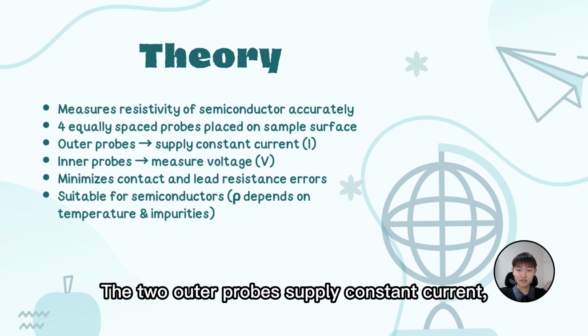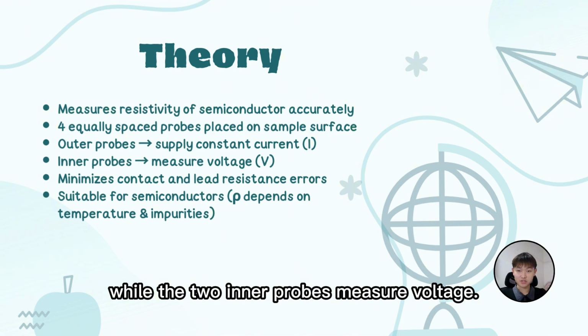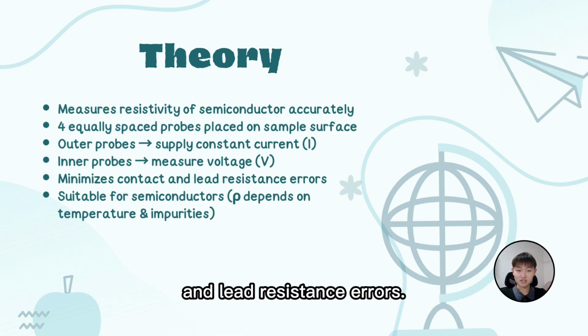The two outer probes supply constant current, while the two inner probes measure voltage. This arrangement helps reduce contact resistance and lead resistance errors.